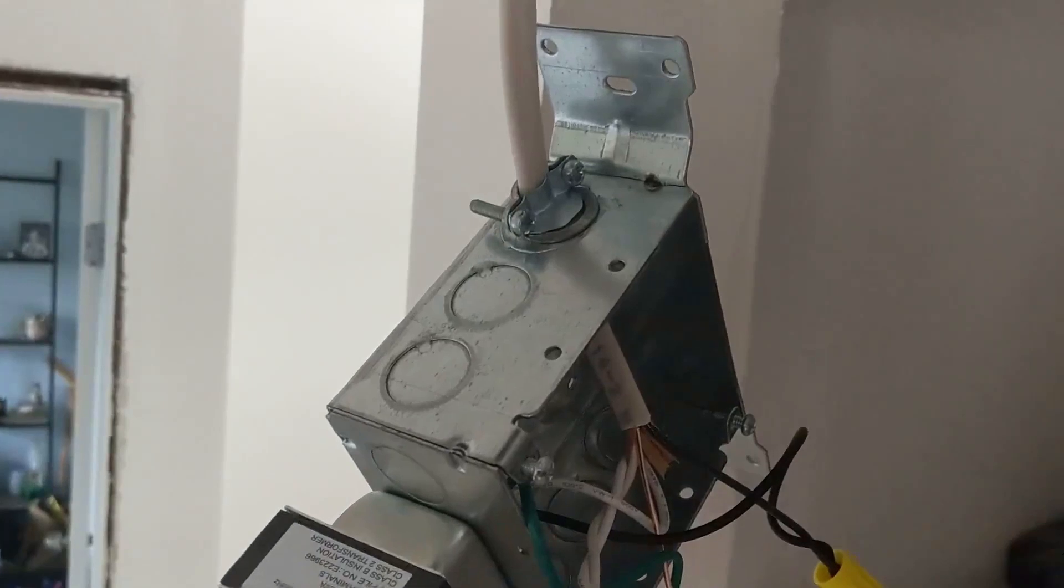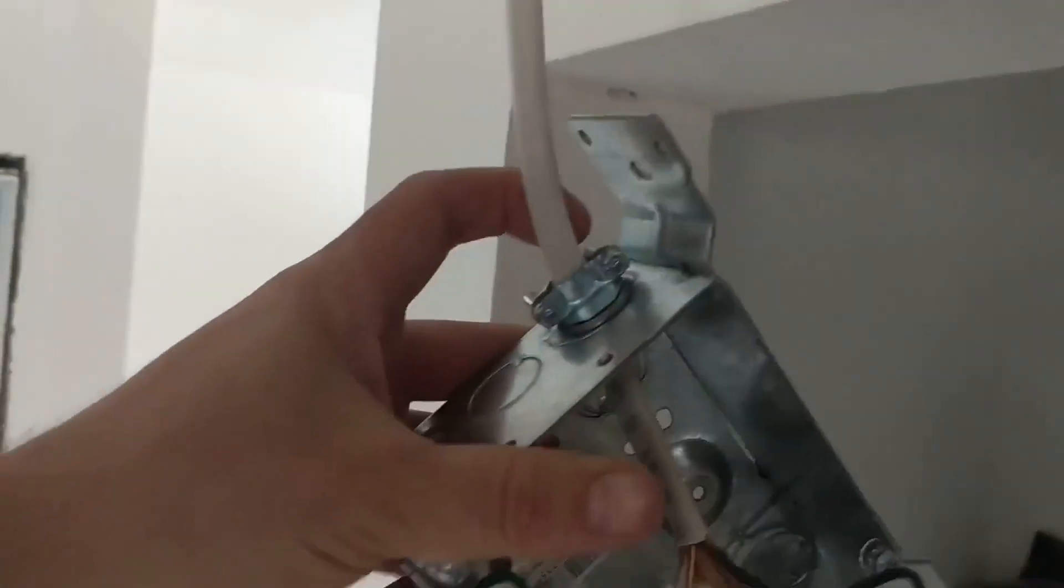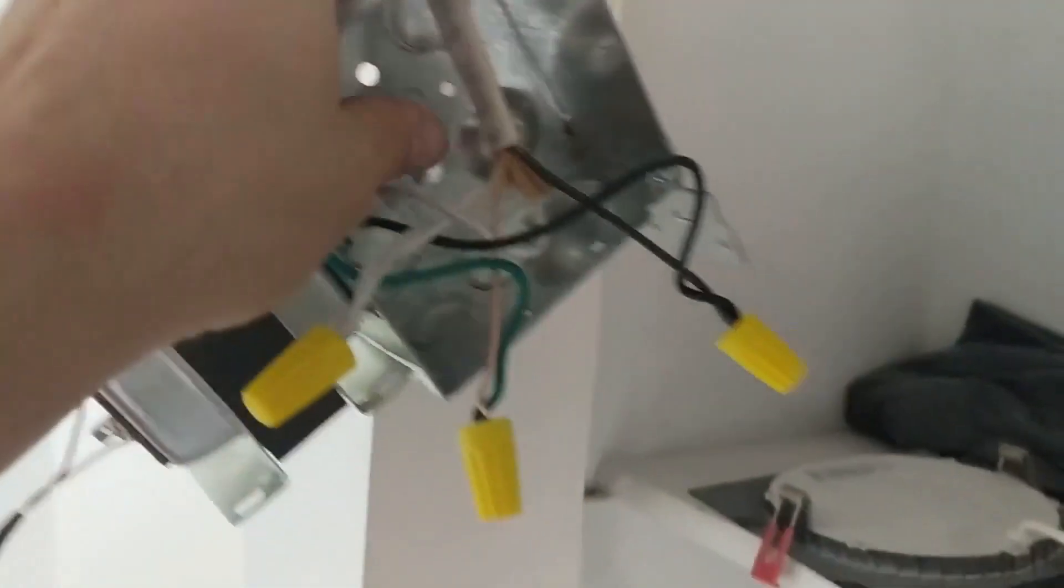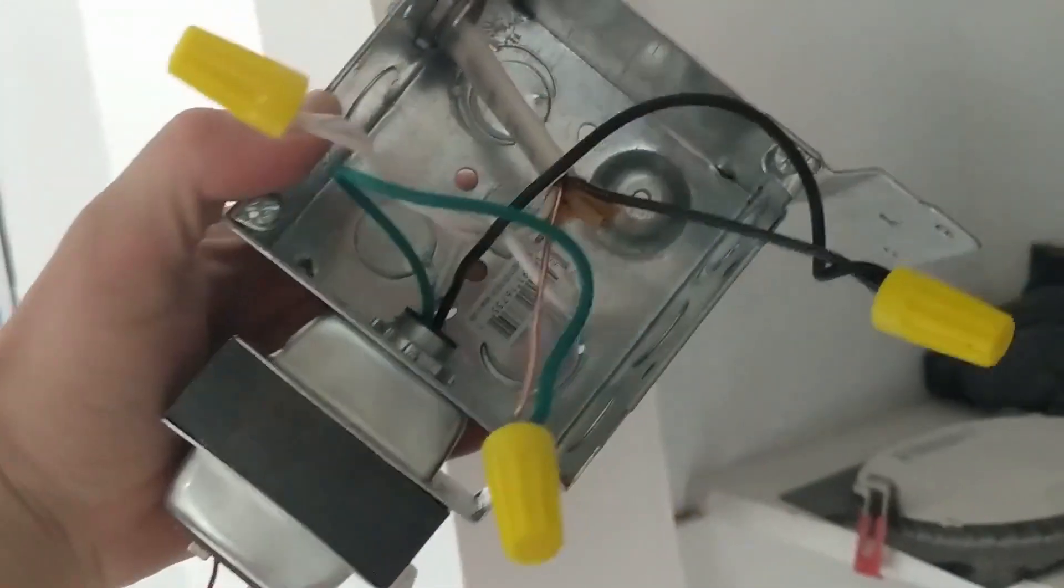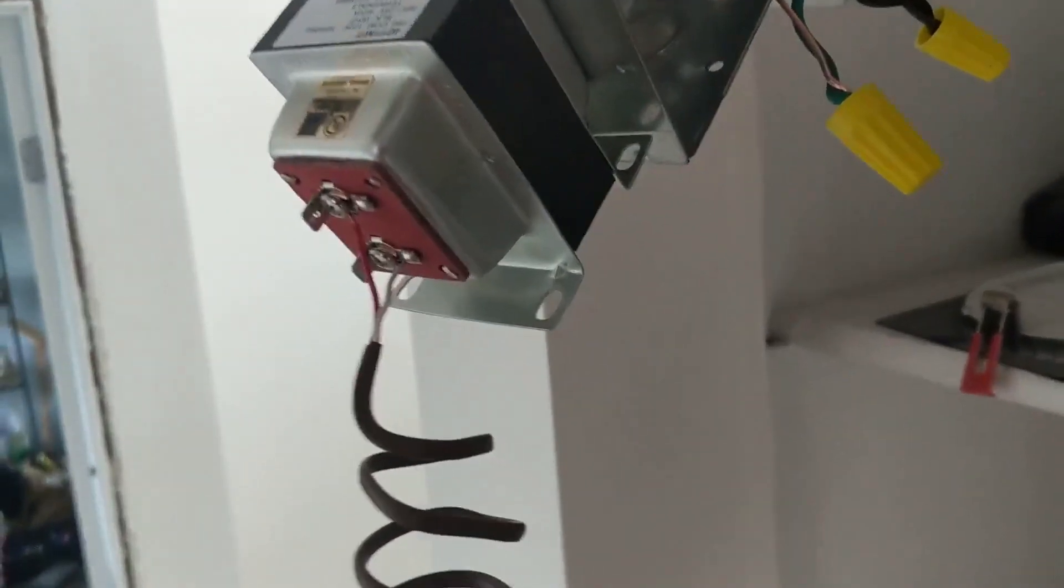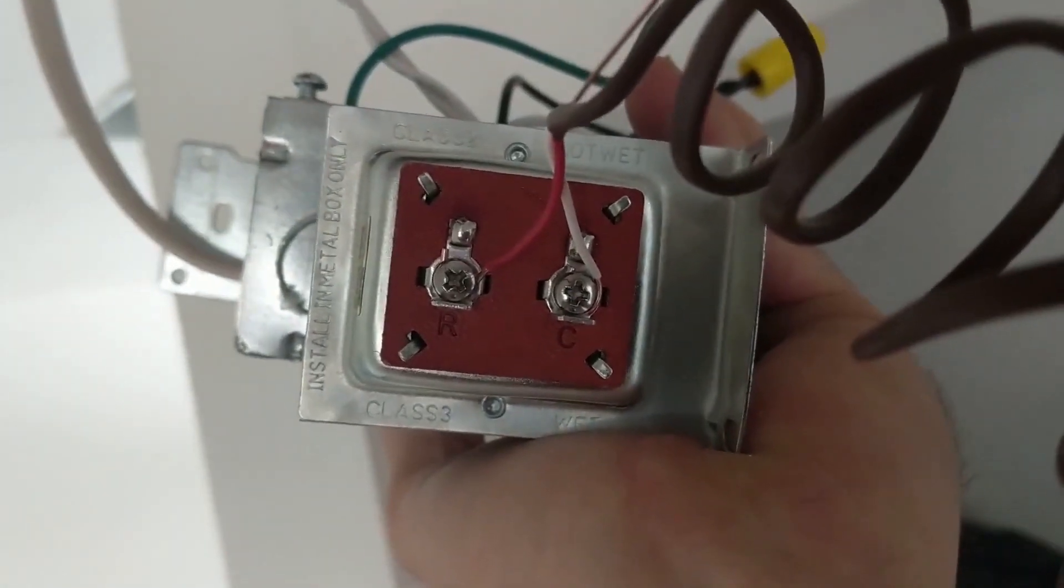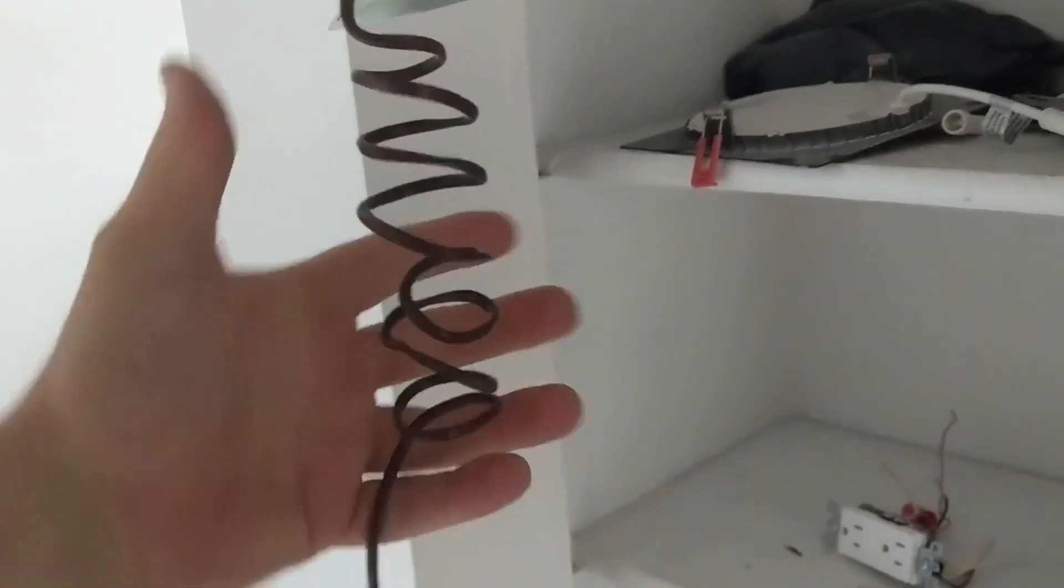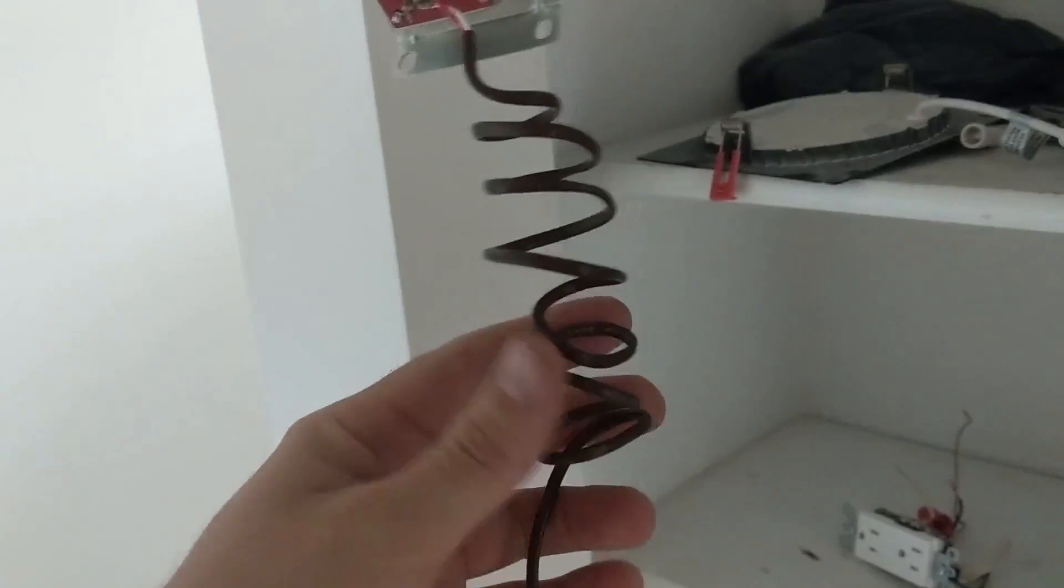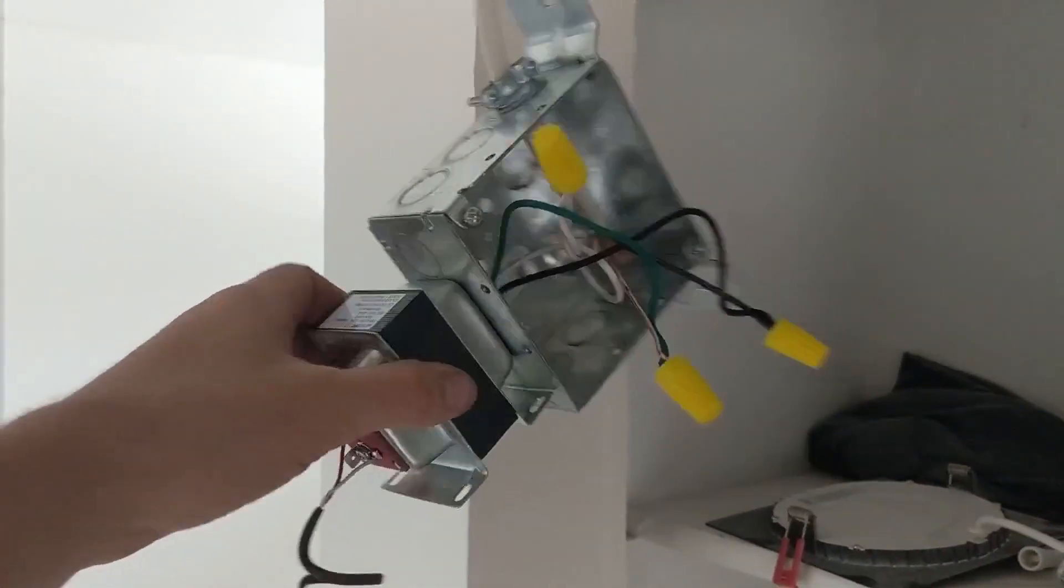Now for the wiring - we've got that little clamp so it doesn't pull out. White to white, green to ground, black to black. I typically ground these boxes, but since this is a 24-volt transformer in the attic, nobody's going to touch it, not a big deal. Red R and white to C. I always like to leave a little squiggle so if this gets pulled there's plenty of wire and it doesn't tear.